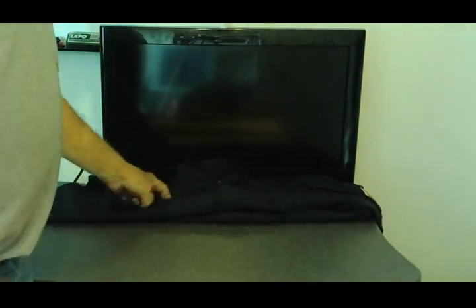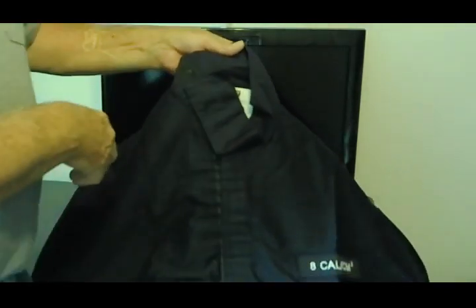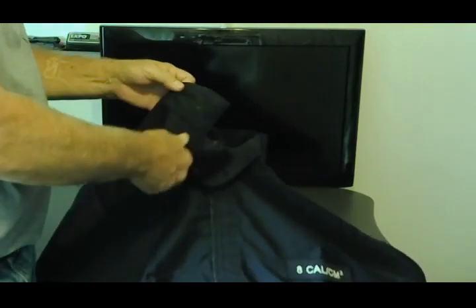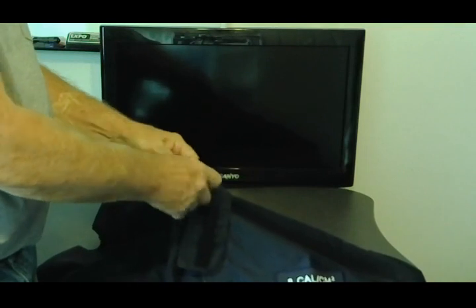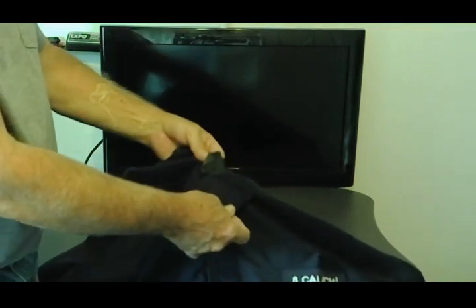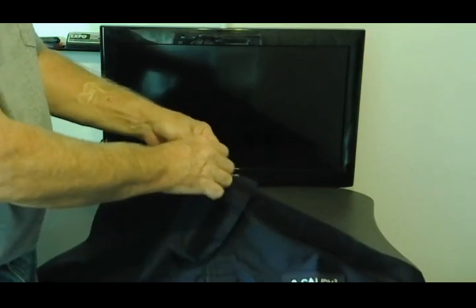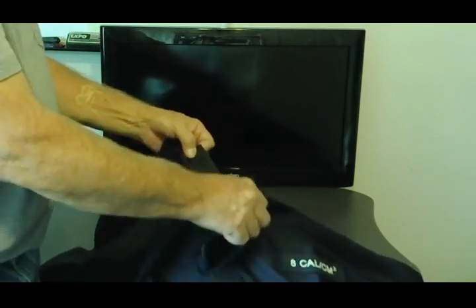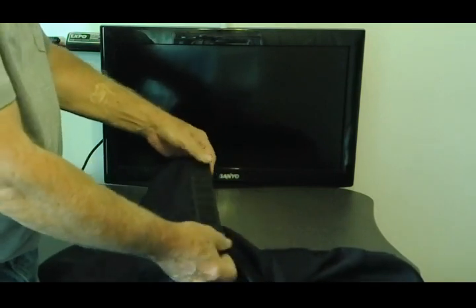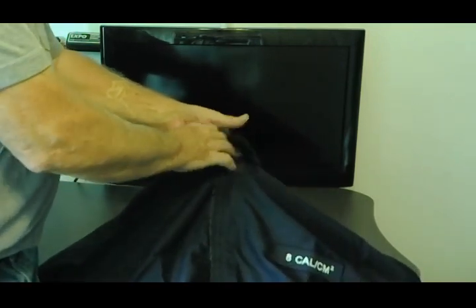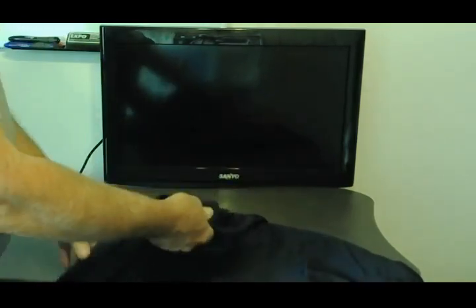Now, following this, we have the electrical arc flash PPE. Arc flash PPE, well, we want to look at this stuff and we want to actually inspect it every single time it's used. For example, right here on this one, the Velcro is ripping. This would be considered damaged and pulled out of service. We want to inspect every bit of it. Where it Velcros up, we want to inspect to make sure there are no holes, no cuts, no tears. We look at the sleeves right here and make sure they're not damaged on any side, no holes, cuts, or tears, or else this should be pulled out of service.